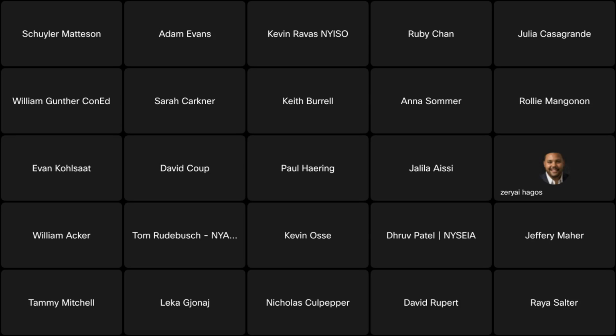Good, thanks, Jeff. And the other thing I would mention is that for some resources, I think you're spot on, Bill, that it will have a one-to-one approach, but at some point we just exceed the maximum capability of a lot of those local systems. That's one issue. The second issue is that the location and method for interconnecting a lot of the large scale renewable resources is not necessarily directly into load substations. It may be at a different segment that has to go up to the high voltage system and then back down to find load again. So in the long term there's potential for a lot of those resources to need additional upgrades to get connected to the high voltage long distance system anyway, even with load growth.